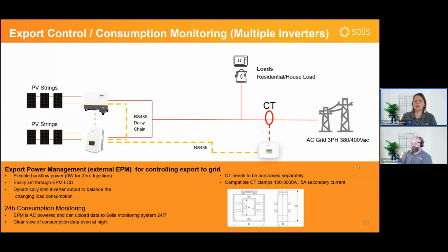If we're talking about three-phase hybrids, these CT clamps we do not deliver, because, as you know, the size of the CT clamp will be decided by the actual value of the current which goes through this grid connection point, depending on the size and number of the inverters, and the size of the loads here, which can be not only residential but even commercial or industrial sites. They can be very high. That's why these will have to be purchased separately by the installers. There's nothing special about them. They only need to have a 5 amp secondary current. This is the most important thing. Otherwise, the primary current can go up to 3,000 amps.